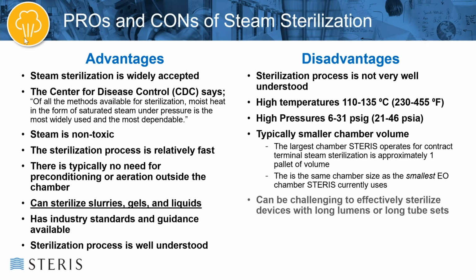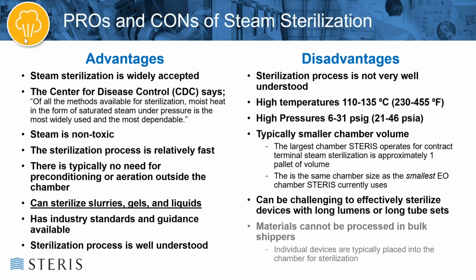With steam sterilization, it can be challenging to effectively sterilize devices with long lumens, such as long tube sets. Sometimes overly complex devices could present problems. Mated surfaces sometimes present problems. And then one of the key aspects to consider for a disadvantage is that materials cannot be processed in bulk shippers.